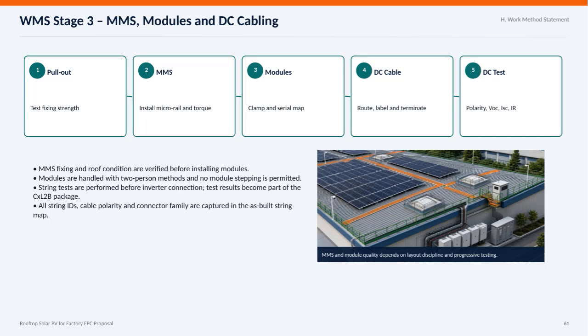On this slide, we're focusing on the key steps in WMS Stage 3, which covers the mechanical mounting structure, or MMS, the solar modules, and the DC cabling. First, we start with the pull-out test to verify the fixing strength of the MMS. This is crucial because the mounting system must be securely attached to the roof to ensure stability and safety. Once the MMS fixing and roof condition are confirmed, we proceed to install the microrails and correctly torque them to specification. Next, the modules are installed using a careful two-person method to avoid any damage, with strict rules like no stepping on modules to maintain quality.